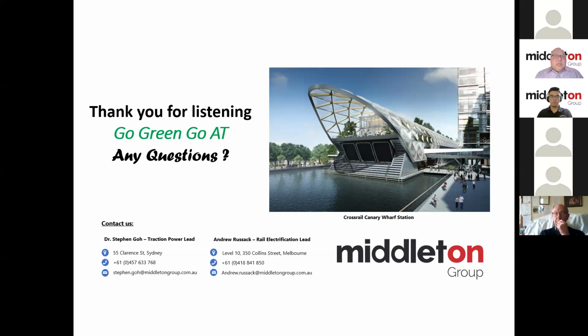Also, there's the new one, the static frequency converter, and you may want to consider that as well. Obviously, there are people with reservations about the static frequency converter because it's relatively new. Not only that, it has a lot of power electronics in the front end, converting from 3-phase to DC, and then from DC back to AC, single phase. So there's a lot of power electronics involved, and any failure of that, and you may think that it doesn't work very well. Also, unlike transformer-based systems, the devices they use are called IGCT, integrated gate-commutated thyristor, as opposed to IGBT.